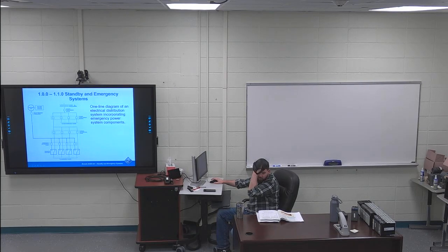I'm looking at figure 1 in your book. That's your normal service. So you have your breaker that comes in, overcurrent devices, more breakers. This goes to non-emergency loads. So if power goes out, these do not come back on. This breaker or overcurrent device over here, whether it's a fuse or a breaker, comes down and feeds this distribution panel, which feeds everything that has to be on the emergency loads.